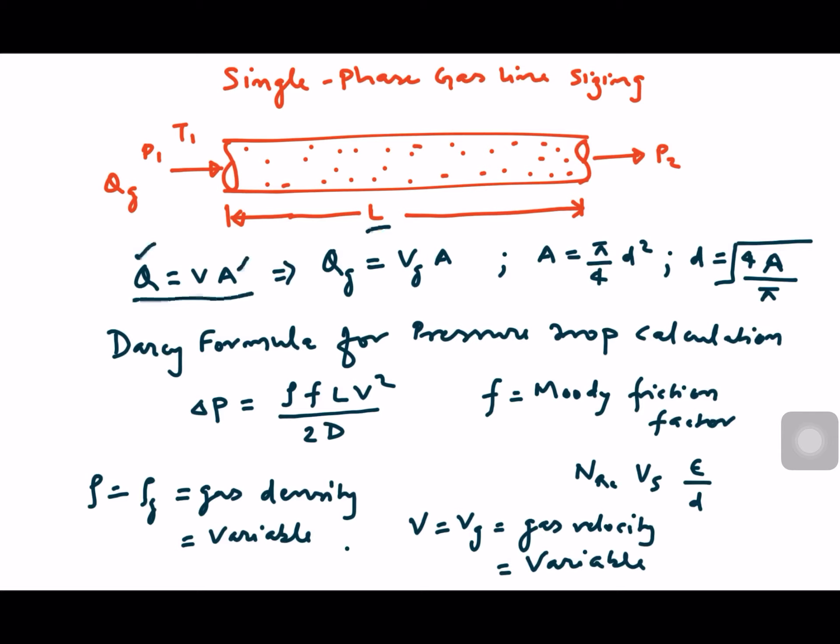For a liquid line, we normally keep the velocity less than 4.5 meters per second for continuous service. For intermittent services we keep the liquid line velocity below 3.3 or 3.5 meters per second. We also use the pressure drop calculation formula, which is the Darcy formula: ΔP = ρfLV²/2D, where ρ is the density of the fluid, f is the Moody friction factor, L is the length of the pipe, V is the velocity, and D is the internal diameter of the pipe. The Moody friction factor is calculated from the Reynolds number and the e/D value.